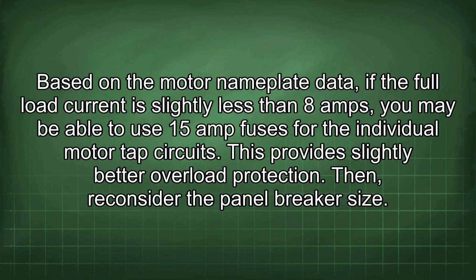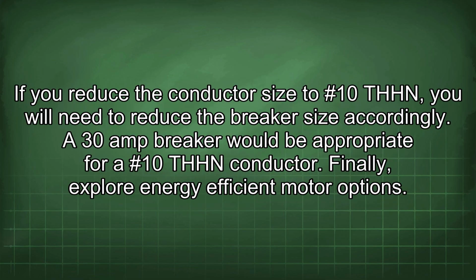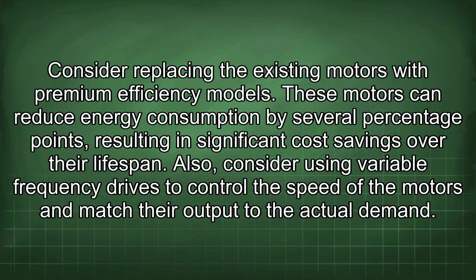Then, reconsider the panel breaker size. If you reduce the conductor size to #10 THHN, you will need to reduce the breaker size accordingly. A 30 amp breaker would be appropriate for a #10 THHN conductor. Finally, explore energy-efficient motor options. Consider replacing existing motors with premium efficiency models. These motors can reduce energy consumption by several percentage points, resulting in significant cost savings over their lifespan.